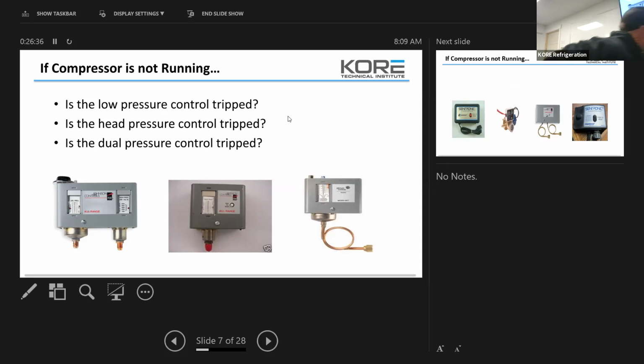So this one right here is these two controllers in one. And because there's not a reset on here, it's going to automatically reset. Meaning it's going to hit head pressure, wait for the head pressure to drop, and try to start again. And it's going to do that and cycle and cycle and cycle, until you fix the condition of why it's tripping off on head pressure.